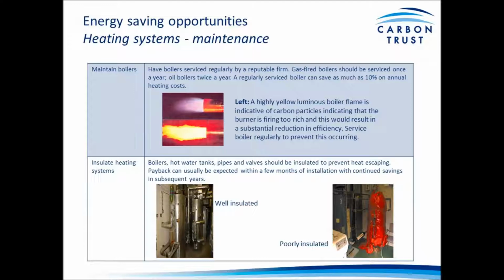Insulation. It's very common that we see this. A question I would ask is, when you walk into your boiler room, is it hotter than the other rooms around it? And often we find that this is yes, and it's due to poor insulation. And insulation is critical to ensure heat is only emitted in areas where you need it and not lost to plant areas or service spaces.